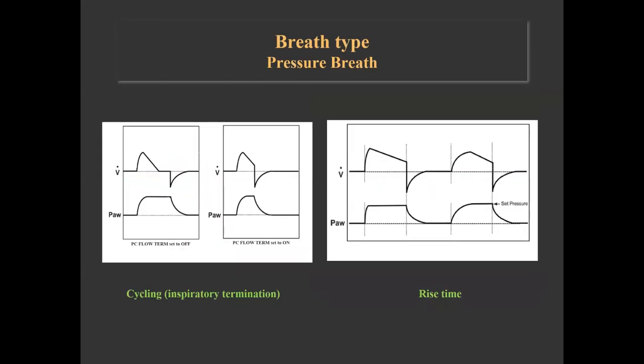Let me review a few concepts of ventilation before describing the LTV interface. The LTV can deliver two kinds of breaths: pressure and volume. A pressure breath is delivered by elevating the circuit pressure to a preset level maintained during inspiration. The inspiratory phase termination is determined by the preset inspiratory time, or terminated when the flow decelerates to a preset adjustable percentage of the peak flow. By default, in control or assist control mode, the pressure breath is time-terminated, as opposed to pressure support where the inspiratory phase is flow-terminated. The cycling mechanism can be optionally changed from the extended feature menu, and the rise in pressure can also be adjusted from there.